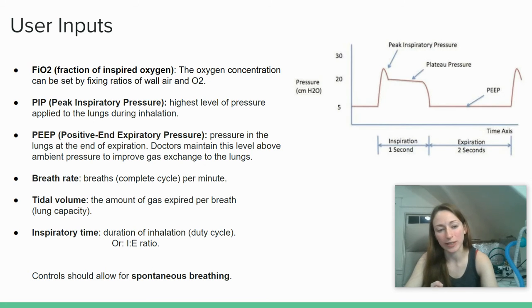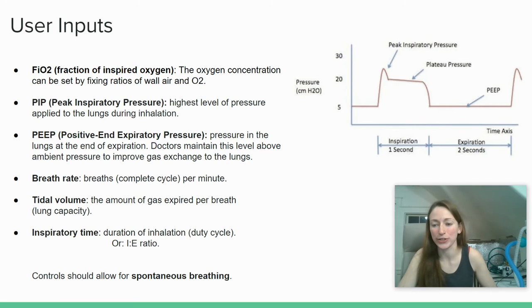Additionally, we want to be able to set the breath rate, the number of breaths per minute, and the tidal volume, that's the amount of gas expired per breath. You can think about this like the lung capacity, which is typically estimated as a function of patient height in adults. And also the inspiratory time. That's the duration of inhalation. So effectively, it's the part of the duty cycle of the breath that corresponds to inhale. You can also see this called the I/E ratio, but effectively it's the same duty cycle consideration.